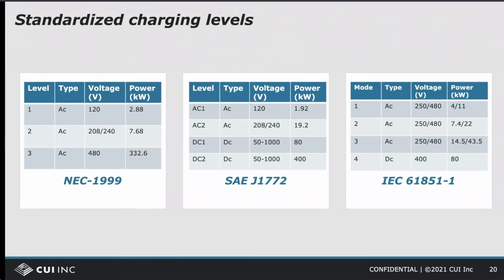Safety standards have been created that classify EV charging stations by power level and type. One of the first standards came from the NEC in 1999, and in this standard, charging stations were divided into 3 levels, all of which were for AC charging. Level 1 defined slow AC charging and used a standard convenience outlet to provide power from the grid. Level 2 was a little bit faster charging and worked off 208 or 240 volt AC and had power levels up to 7.68 kilowatts. Level 3 was the AC fast charging level, which operated off of 3-phase 480 volt power and was much faster but also required a much larger and more expensive service equipment.